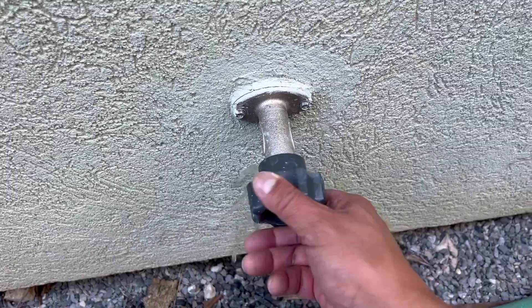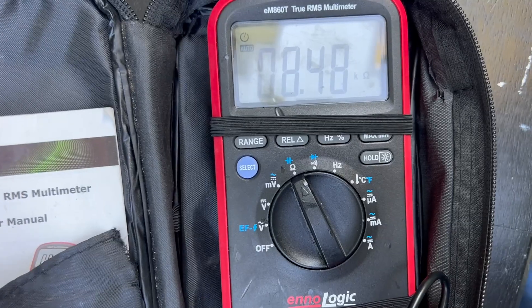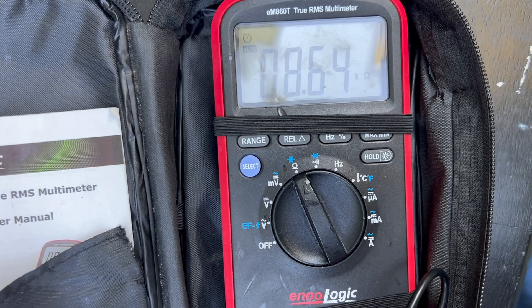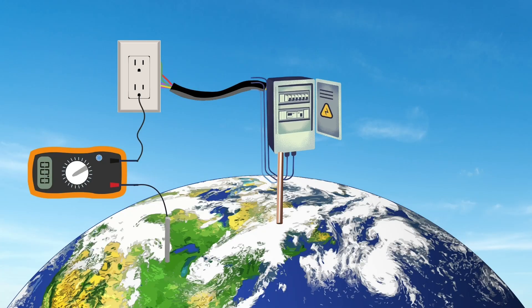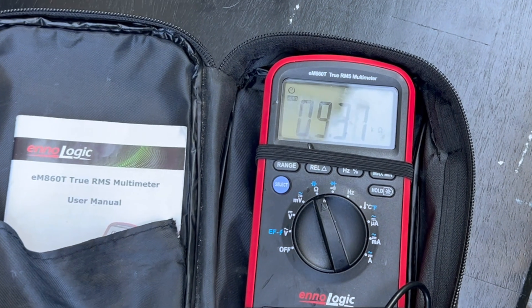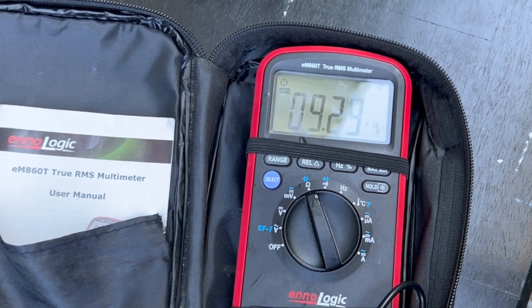I'm going to turn on the water. Checking the multimeter, you can see it's less than 9 ohms resistance. Keep in mind what we're measuring is the resistance from the outlet, through the house wiring, down to the main ground, and then to the earth and to the earthing rod. So 9 ohms resistance is very minimal, and this is a very well-grounded house.